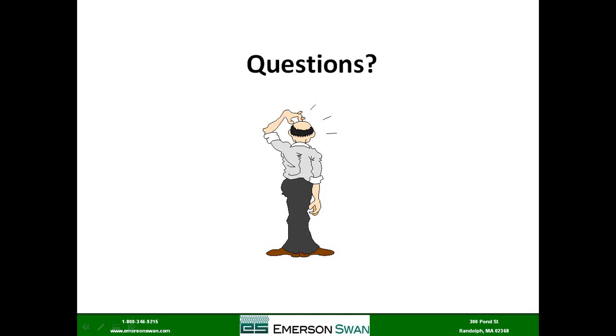Here's a question about the PC700. Will a PC700 control work with a boiler that already has an older Beckett heat manager on the burner? There's a good question. Well, you've got to fight each other, wouldn't they? Clashing technologies, yeah. It's either one or the other. I mean, the heat manager is an inferential control, which is counting cycles. It's looking at the cycles of the circulator, the cycles of the burner, and it's making a determination on how the boiler should run. A PC700 is an outdoor reset. So I think they'd fight each other. I wouldn't. It's either one or the other. You can't do both. I think that makes sense.